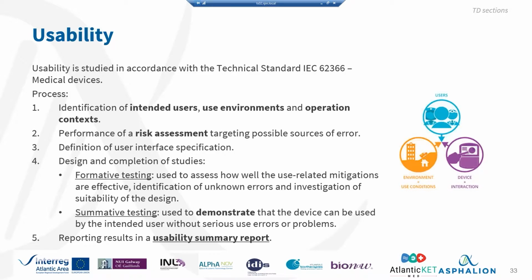This is studied in usability. Usability is studied in accordance with technical standard 62366, which is specific to medical devices. And the testing of usability of the device particularly aids at indicating that your device complies with the requirement of usability. So what is the process to study this usability?